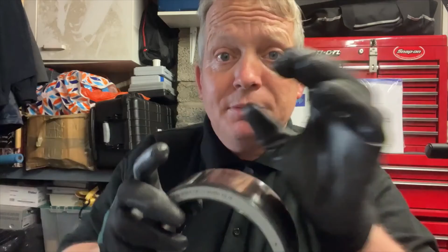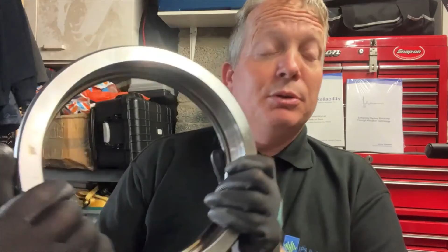And what would you expect to see in the outer race? If you've got the outer race here in the motor, which is stationary, would you see false brinelling all the way around? But you think about it, if the rotor's stationary like that, and it's got that slight micro movement, it's literally just going to be in a load zone. And the bearing's pretty huge, which is good because I can put it all around the camera. So if I find that there, here we go. So you can see there, nothing at all.